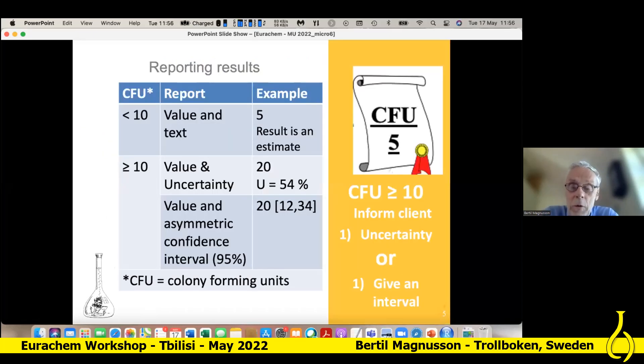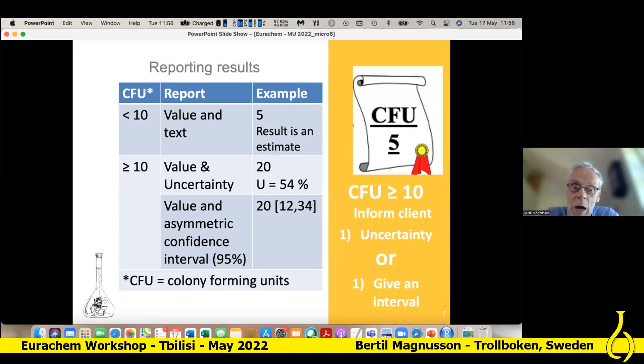One focus of my presentation is how to report results. If we have very low results, we talk about colony forming units — that could be a bacteria, for example. If the number of bacteria we count, this is the CFU, is less than 10, we can just report a value and some text. But if we have values from 10 and above, we can actually report a value and uncertainty. We could talk about a limit of quantification if you think about chemical measurements. We can report the value and relative uncertainty, or we can report an asymmetric confidence interval.